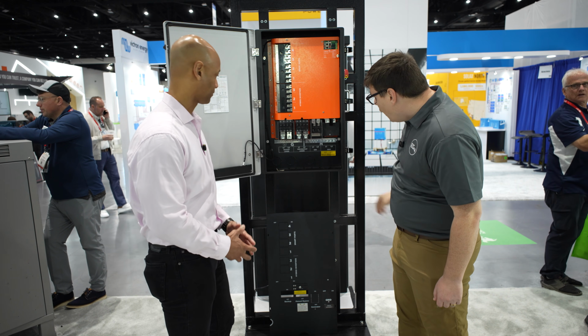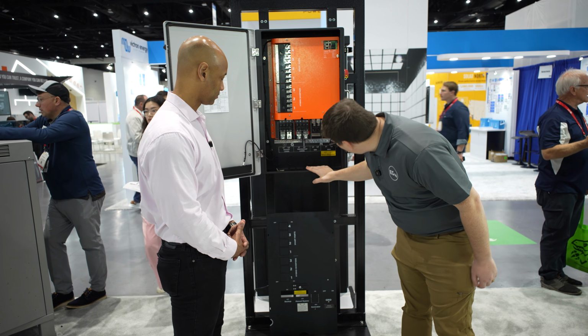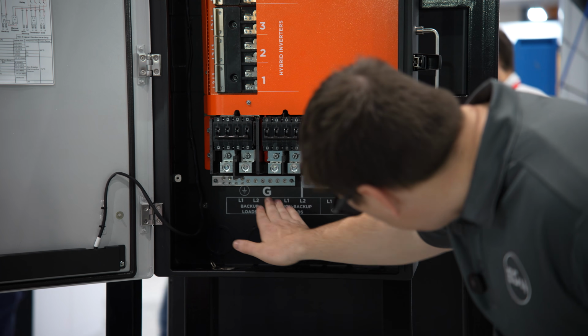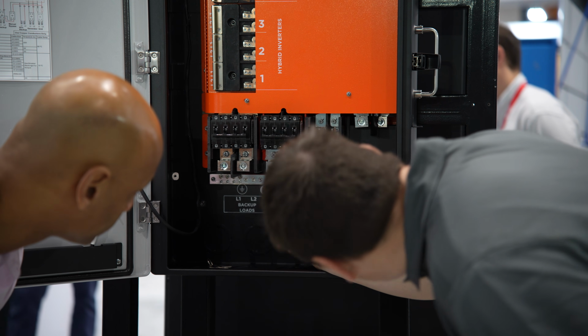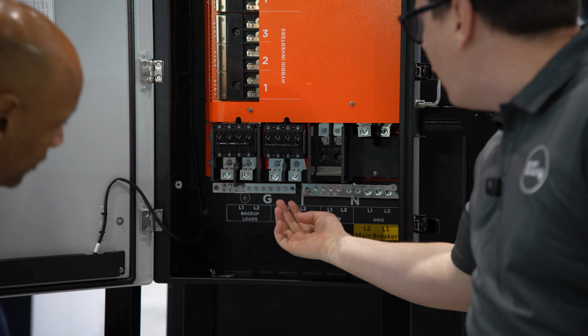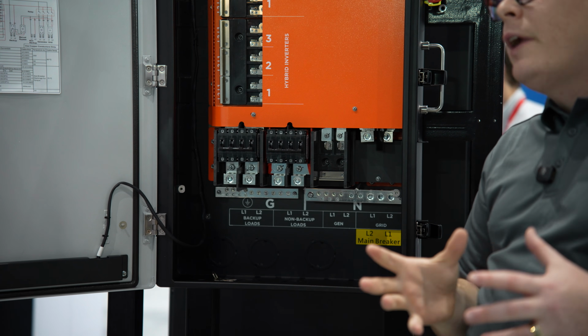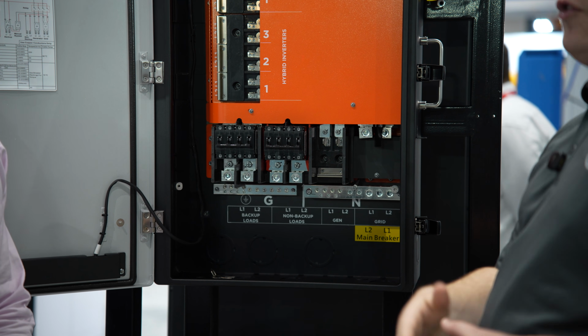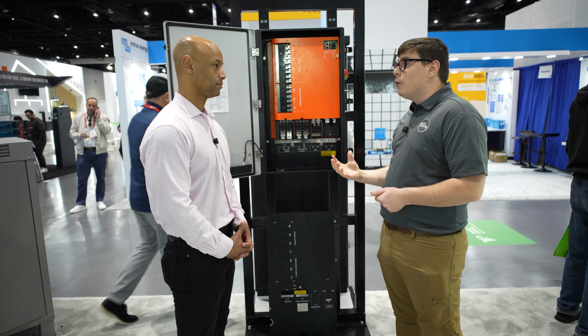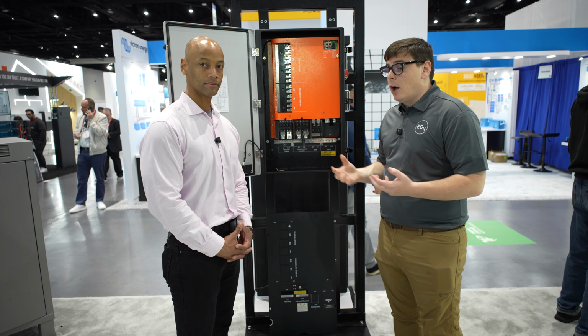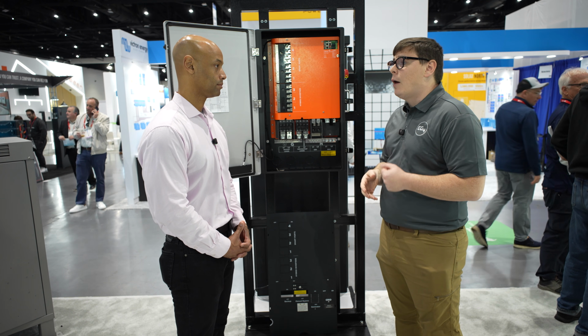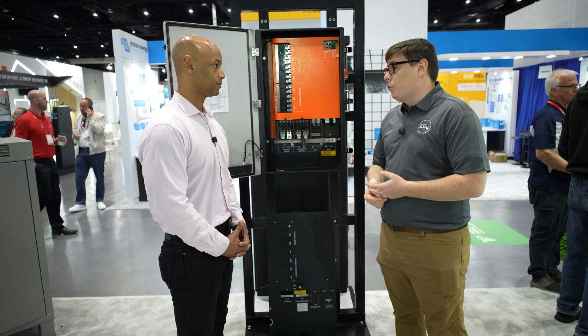We also have a 200 amp pass-through right here for the non-backed-up loads. So we're able to not only back up a 200 amp panel in a house, but we can actually run a second panel through this feeder tap that is not backed up. So you could handle a good amount of power even on a 2-breaker panel house.